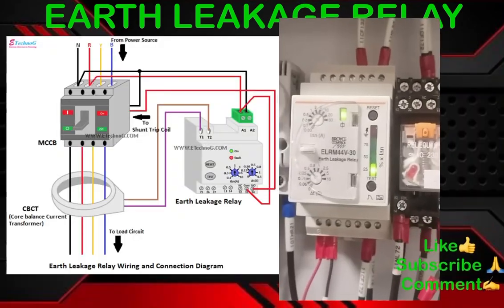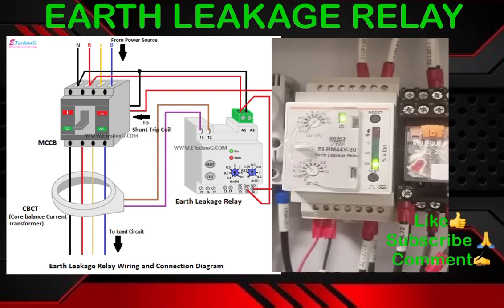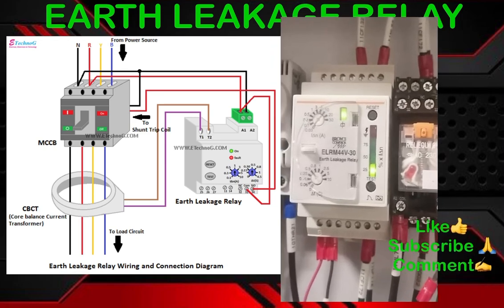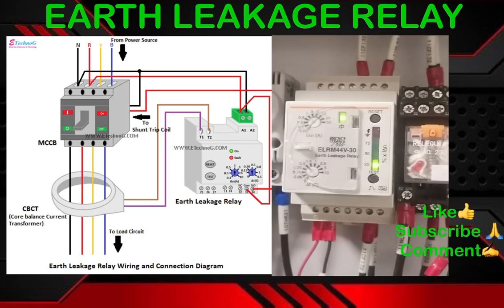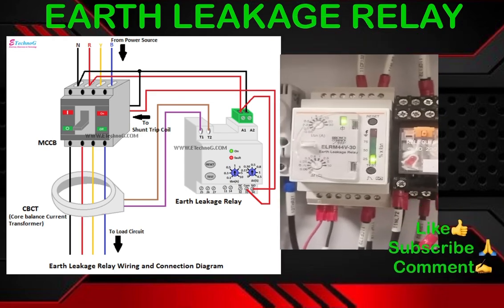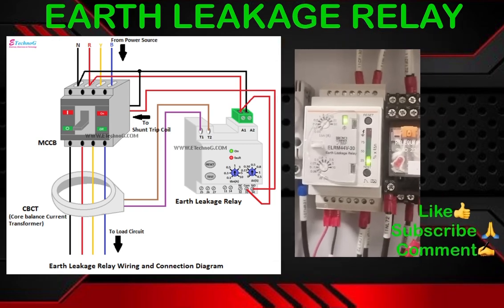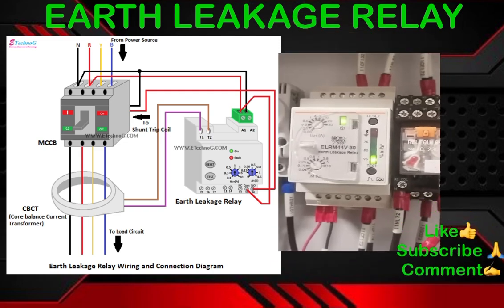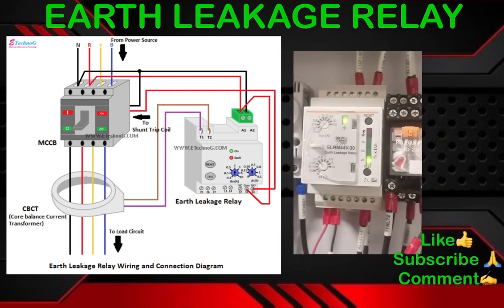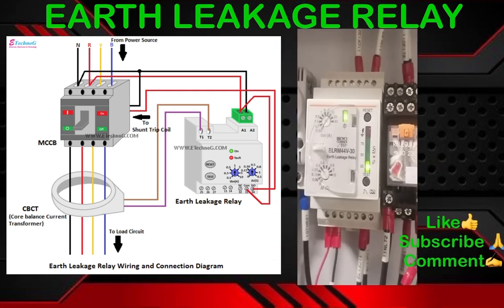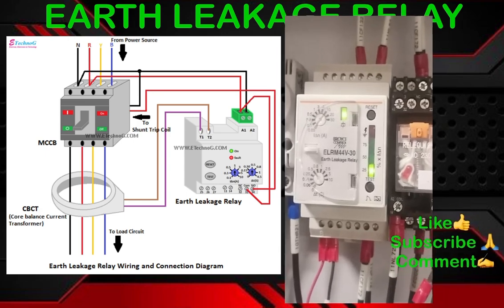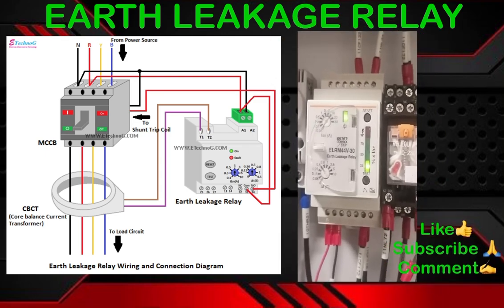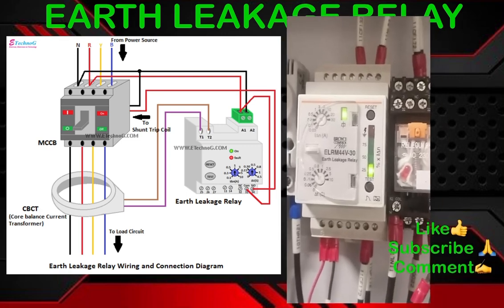Now we will discuss the electrical wiring connection. On the left side you can see the wiring diagram, and on the right side is the earth leakage relay. In the CBCT, all four cables — three phases and neutral — pass through it. Two output cables from the CBCT connect to the earth leakage relay. The auxiliary supply of 230V from phase and neutral connects to the auxiliary terminals. The two bottom cables connect to the shunt coil, so if earth leakage occurs, the shunt coil is energized and the breaker trips.